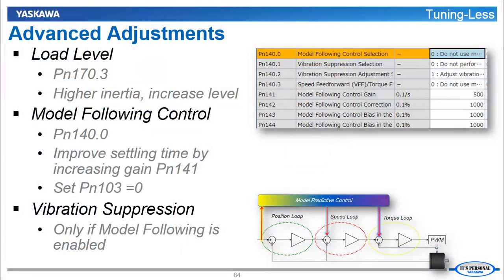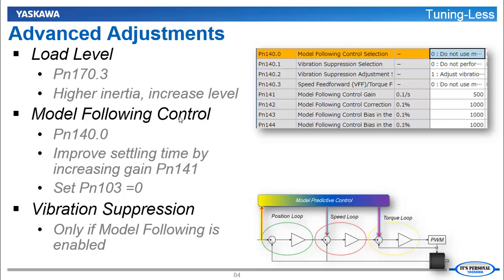But if you had a machine with a changing load and a constant frequency of vibration, then in this specific and special case, you may want to go through with these advanced adjustments. For most mechanical systems and actuators, you don't need to go through these advanced adjustments. And remember if you don't have a changing load and those basic adjustments don't give you the response you need, it might be time to go on to Auto Tuning instead of spending more time with the Tuningless function.